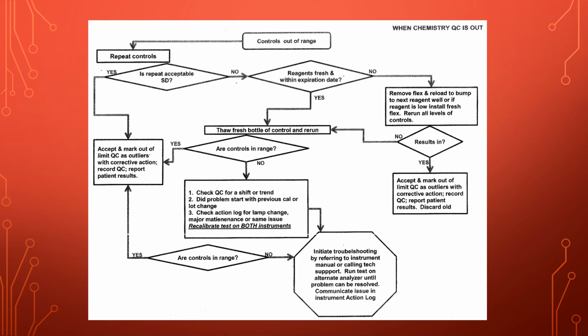Check the expiration dates of all your reagents and control material before repeating the controls, because then you'd at least be able to explain. In some parts of the lab, if you get 3 fails, it really starts causing a lot of problems. In microbiology it does anyway. We have to start doing things for 30 days. So don't waste a run. Make sure you check your expiration dates before you run things the second time.